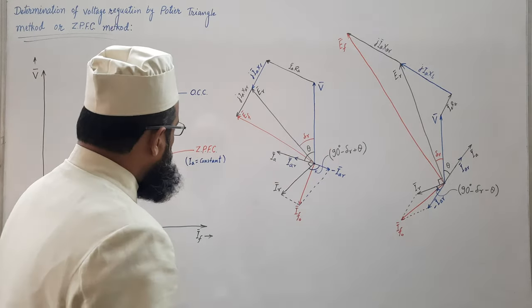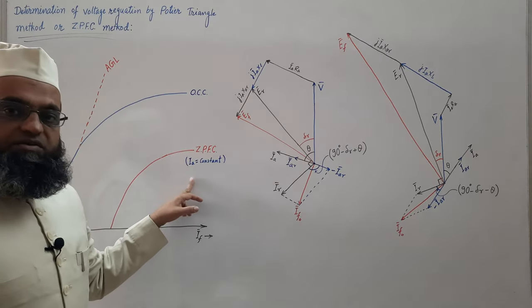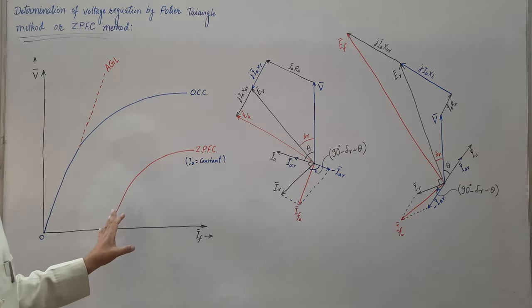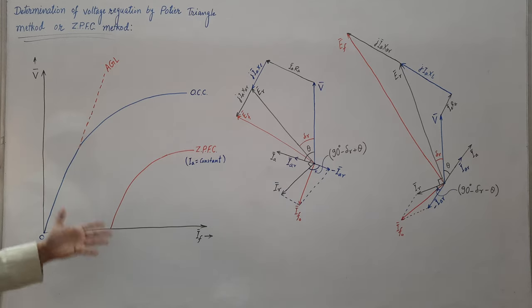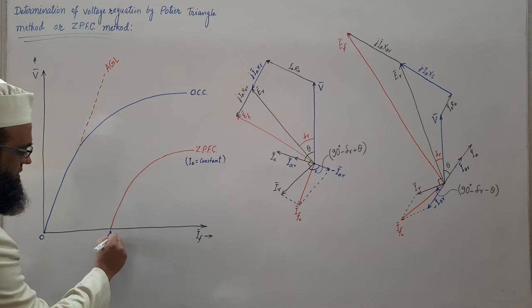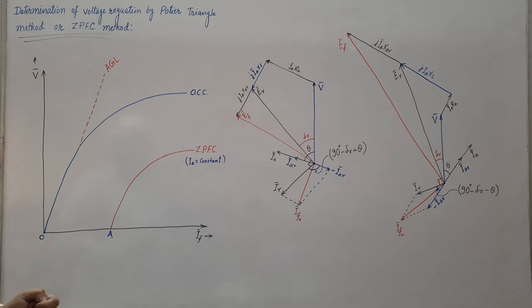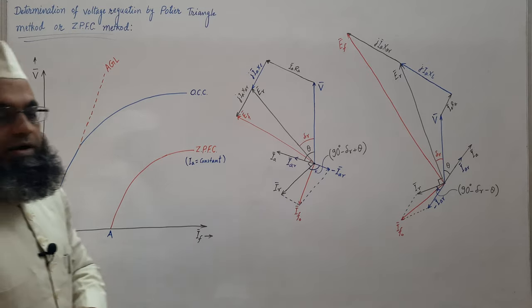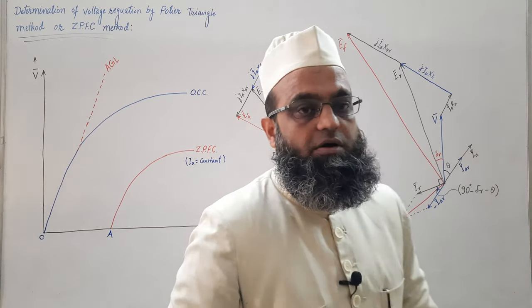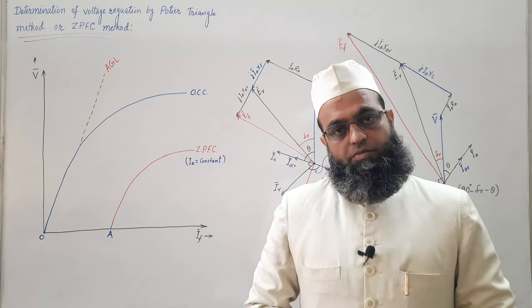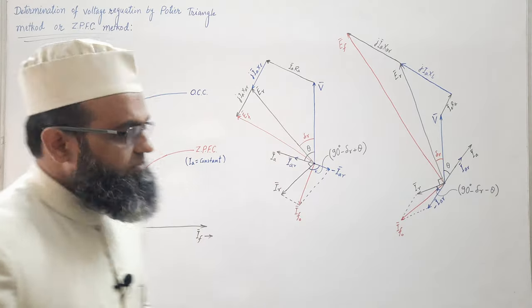Step number two: perform the zero power factor test and draw the ZPFC on the same axis. Let us mark this point as A. In the previous lecture we already discussed ZPFC, and we know that OA, the field current OA, is the field current required to overcome the armature reaction drop as well as the leakage reactance drop.